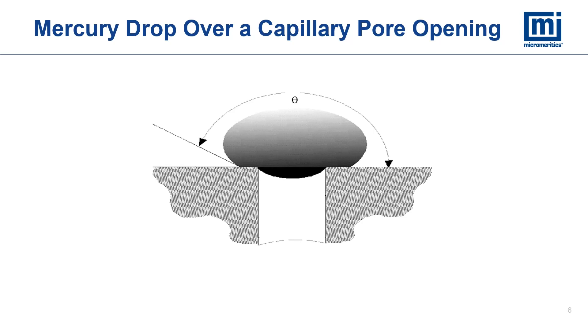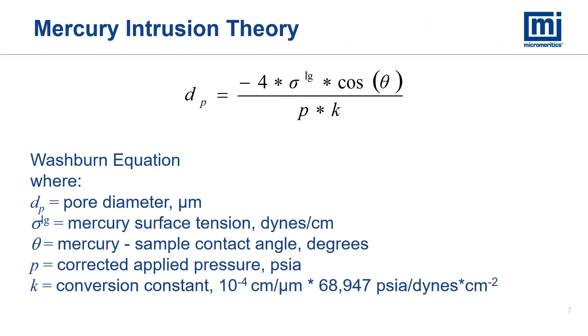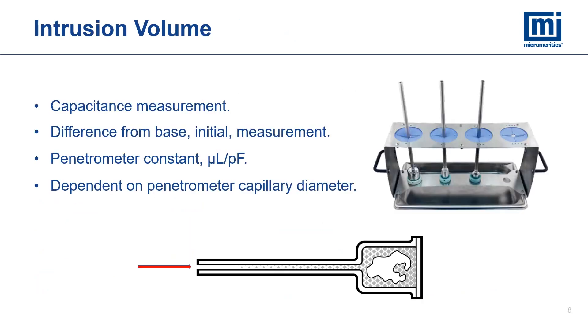Here we see a mercury droplet sitting over the opening to a capillary pore. Notice the definition of contact angle between the mercury and the surface — this is at the advancing edge of the droplet over the sample surface. The diameter of the pore being filled can be calculated from the Washburn equation, where the equilibrium applied pressure P is used with the surface tension of the mercury sigma, and the contact angle between the sample and the mercury theta, along with a conversion constant to keep the units straight to calculate the pore diameter. A change in capacitance as the mercury intrudes into the pores is recorded. Using a constant based upon the internal and external diameters of the penetrometer capillary stem, the capacitance change is converted into the volume of mercury intruding into the sample. This intrusion volume, recorded along with the applied pressure at which it occurs, forms the basis of the cumulative intrusion volume as a function of pore opening diameter.